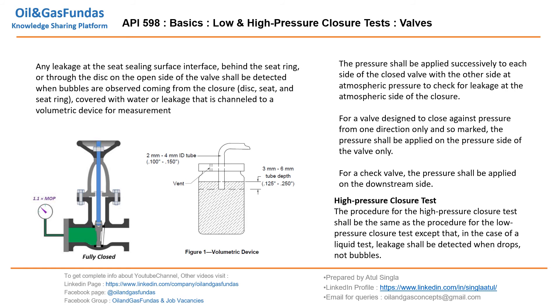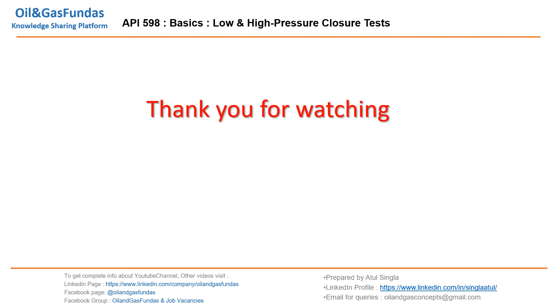This is how low and high pressure closure tests are performed. All terms, conditions, and requirements are given in API 598 — for which valve to perform the test, at what pressure, and for what duration, everything is mentioned in tables one, two, three, and four. Thank you for watching — see you in the next part.